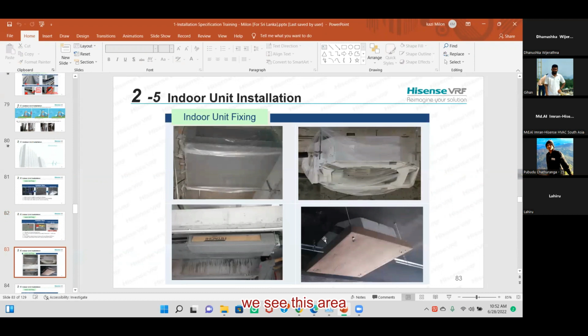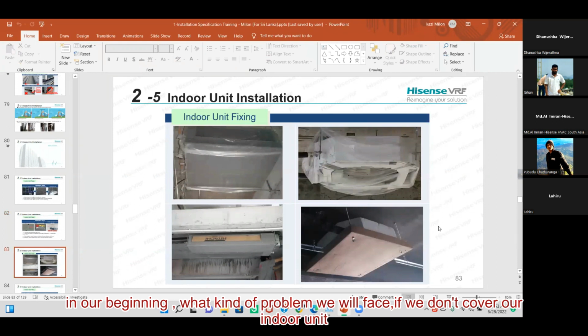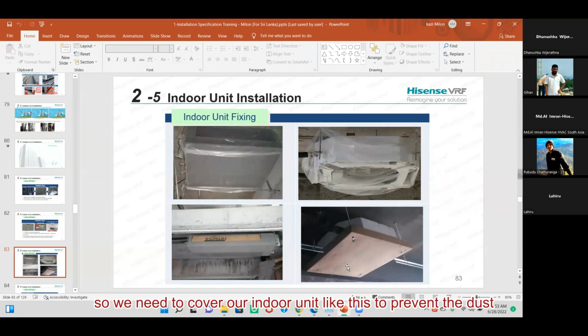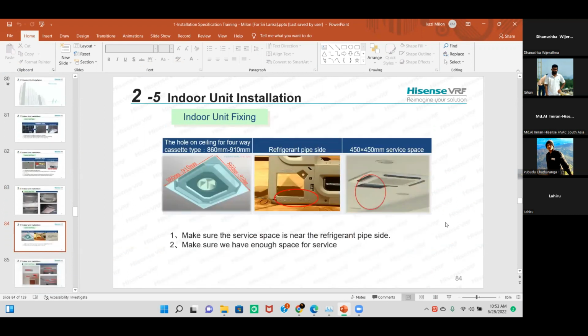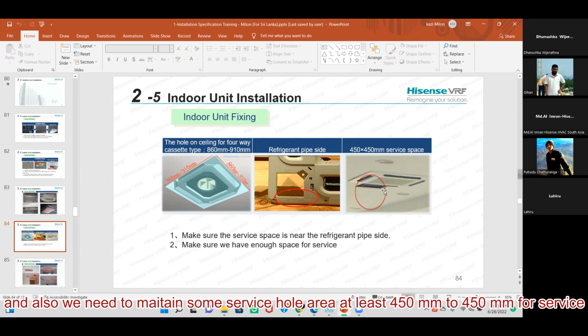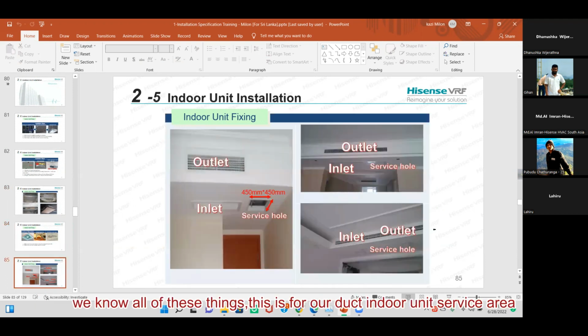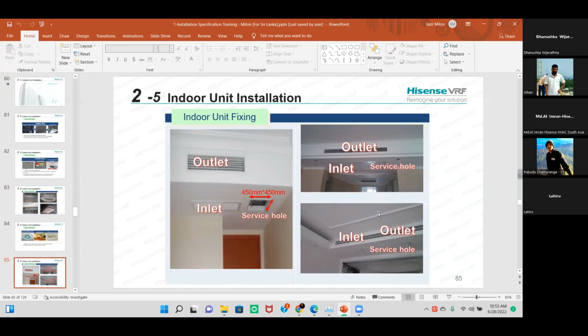We see this area in our beginning. What kind of problem will we face if we don't cover our indoor unit? So we need to cover our indoor unit like this to protect it from dust. And also we need to maintain a service hole area of at least 450 mm by 450 mm for service space. We know all of these things. And this is for our ducted unit areas.